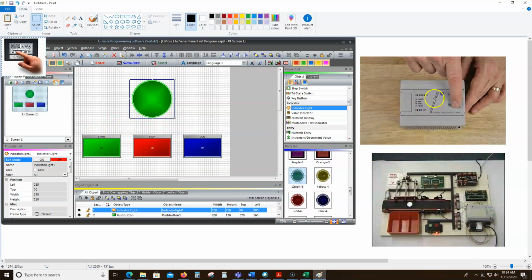So inside of your PLC, you'll need to have those storage bits be in OR with your actual button. So whether I press this real button or whether I press this virtual button, my conveyor is going to come on and latch. Whether I press this real stop or this virtual stop, my conveyor is going to stop. And that's pretty much it. So it's not that hard.